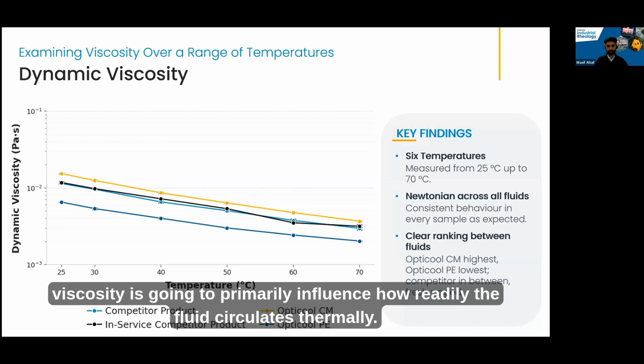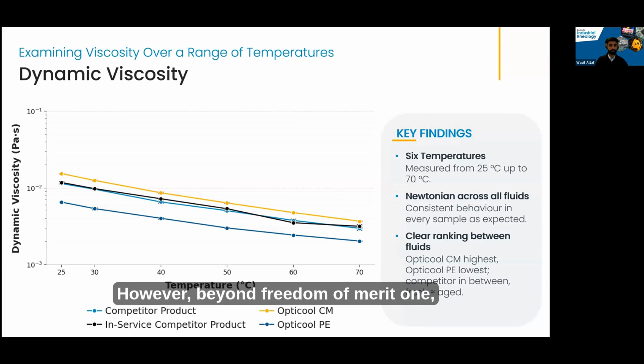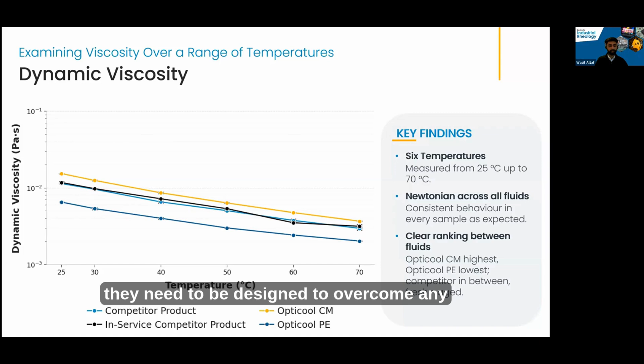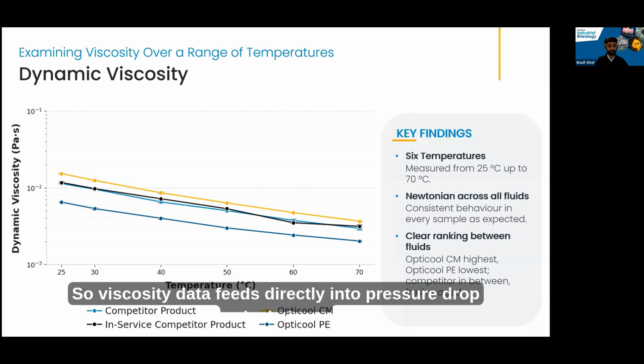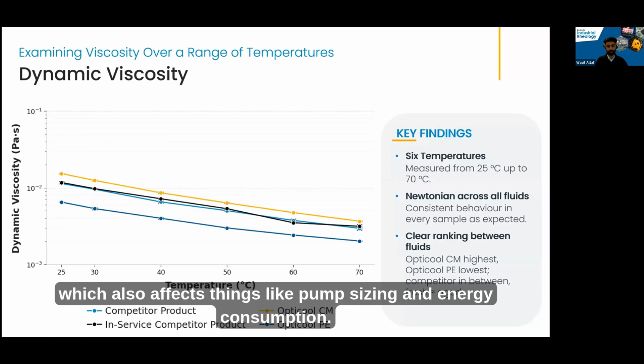Now, for figure of merit 1, viscosity is going to primarily influence how readily the fluid circulates thermally. However, beyond figure of merit 1, viscosity data is practically useful in a couple of ways. For any engineers present who are used to designing pumps, if you've got a forced convection system, it needs to be designed to overcome any pressure drop to actually push that liquid through. So viscosity data feeds directly into pressure drop calculations, which also affects things like pump sizing and energy consumption. And this is going to be related to figure of merit 3, which Bret will go into further later.